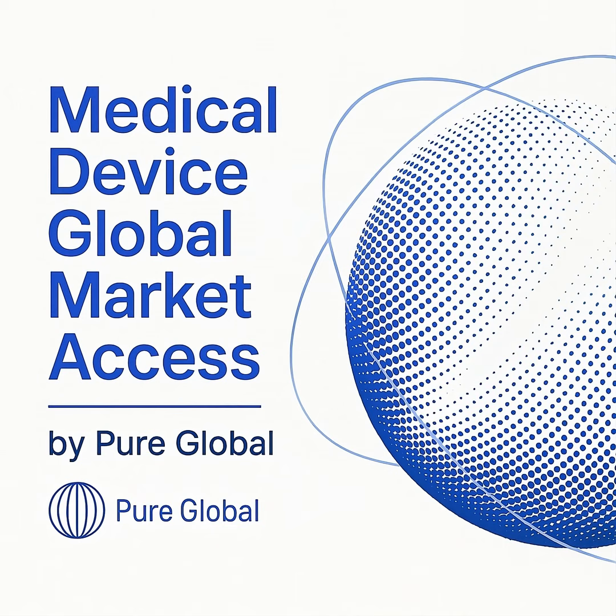Third, your regulatory team must become experts in the new human factors section of the eSTAR portal. We advise not waiting until you are ready to submit. Explore the template now to understand the data entry requirements and document upload functionalities for each category. Finally, reevaluate the risk profile of your entire device portfolio. You need to proactively classify your upcoming submissions into one of the 3 categories to properly scope the required HFE UE activities and resource allocation. A misclassification could lead to requests for additional information and significant delays in your review timeline.